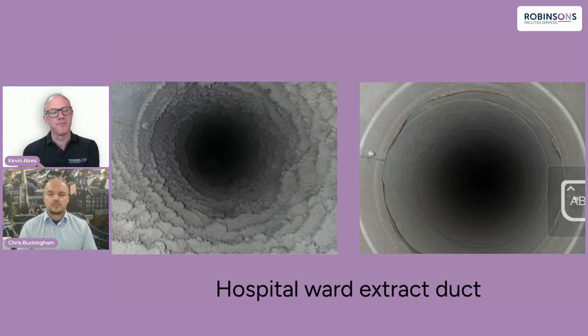We talked about grease potentially causing fire - can dust cause a fire risk too? Yeah, it is. Within normal ventilation you generally have blade dampers - they could be volume control dampers, which adjust the volume going in or out, and also fire dampers like we mentioned before. Anytime you have assets within the ductwork, it's the perfect surface for dust to build up on. With large quantities of dust built up, a slight spark or anything like that will cause it to ignite. It may not generally start a fire, but if you had a whole ductwork system and one spark within that, there's a very good chance you'll have a fire issue. Dust definitely is flammable.